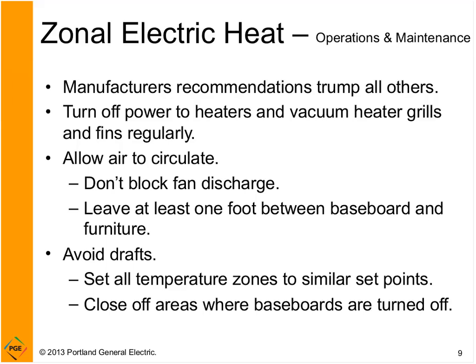So for the wall units with the blower motor and fan. And for the baseboards, leave at least 1 foot between the baseboard and furniture. You don't want to create any fire hazards, and you want to allow the heat to be distributed as best possible. Also, avoiding drafts is important. Set temperature zones to the same or similar set points, whatever it may be, 65, 70 degrees. And if tenants do zone the system, in other words, intentionally not heat certain areas, make sure that the areas are closed off when the baseboards are turned off so you truly are heating only one zone or several zones.